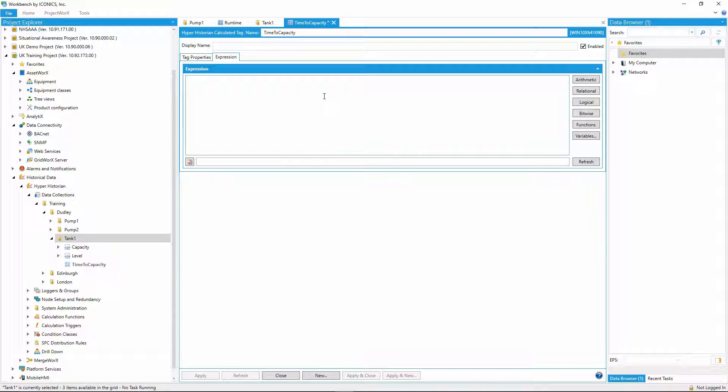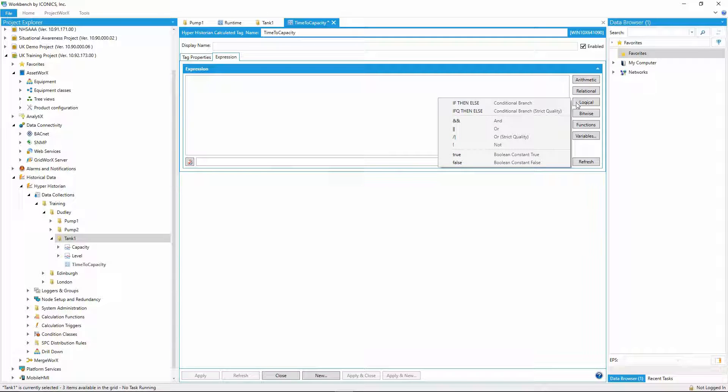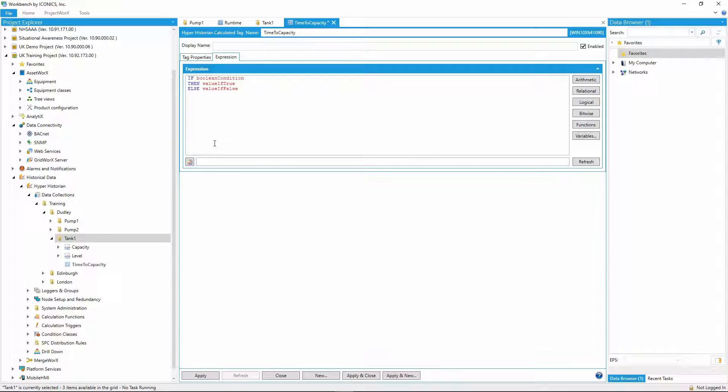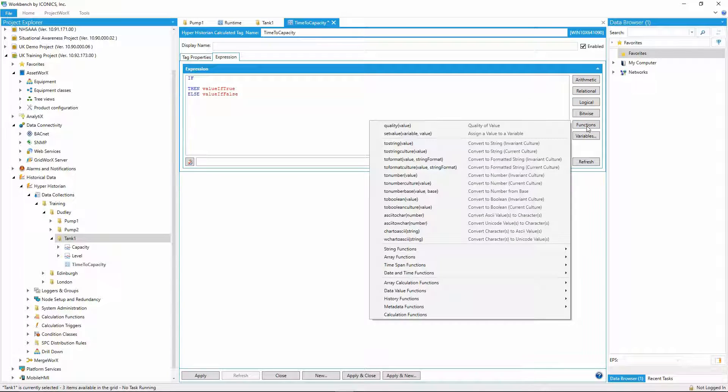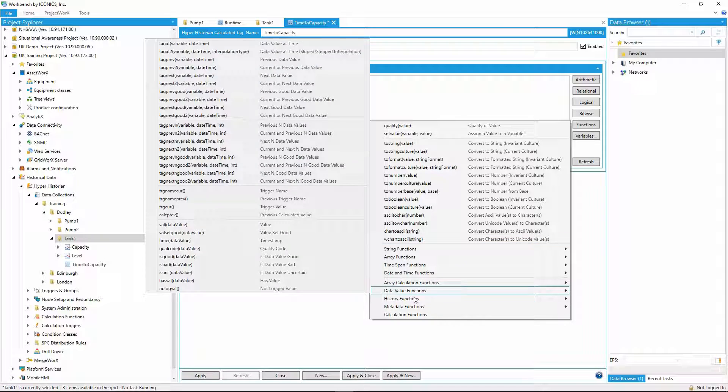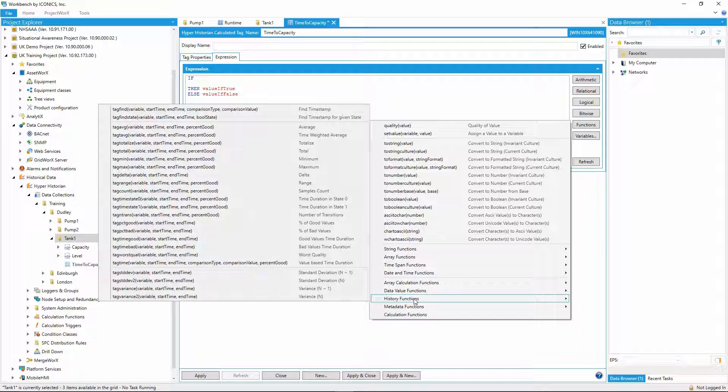I'll start off with an if-then-else statement, since I only want this calculation to evaluate if the tank is filling. For the if, I need to evaluate whether the tank is actually filling or not, so I'll use the tag delta function to check if it returns a positive value.